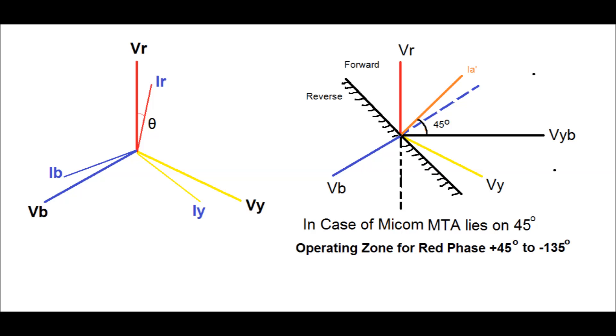Now, for the MICOM relay, the maximum torque angle lies at 45 degrees. That is, the fault current IA' at R phase will be leading the reference voltage phasor VYB. Therefore, the operating region for red phase fault will be from plus 45 degrees to minus 135 degrees. Beyond this operating region, the relay will not sense the fault current.